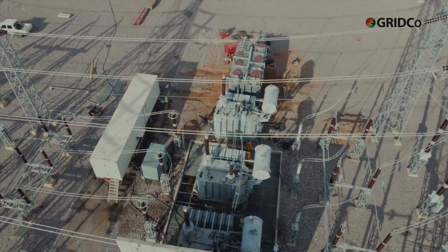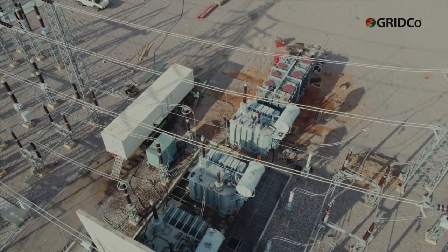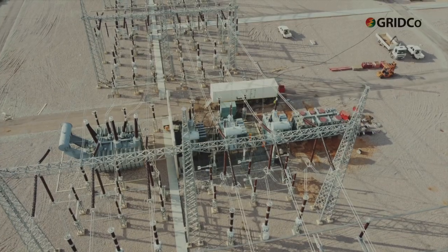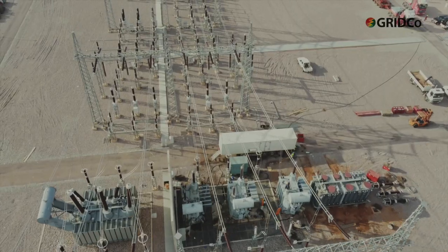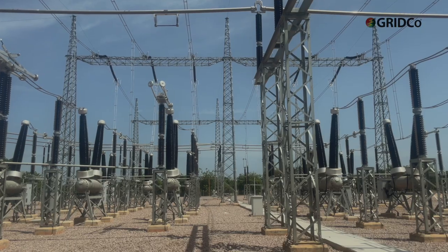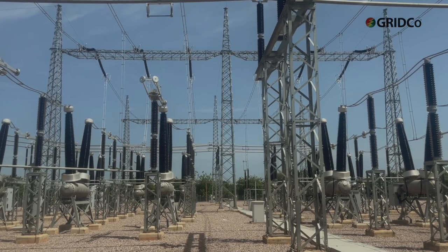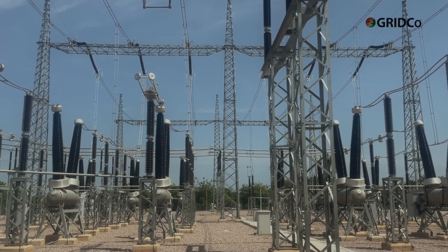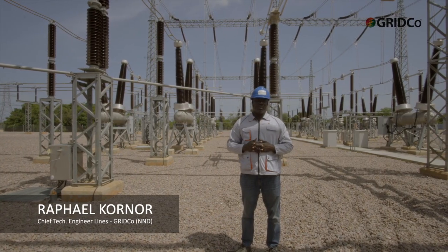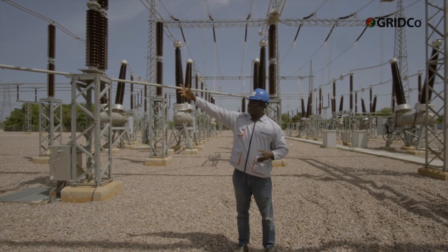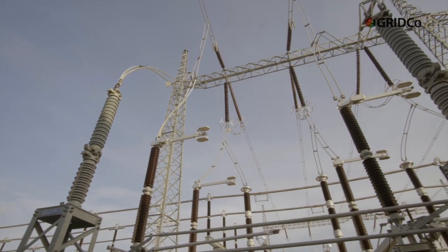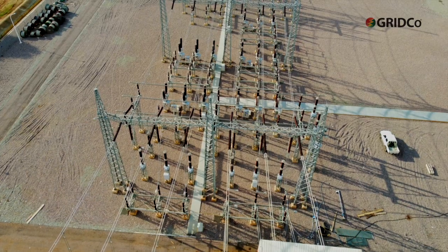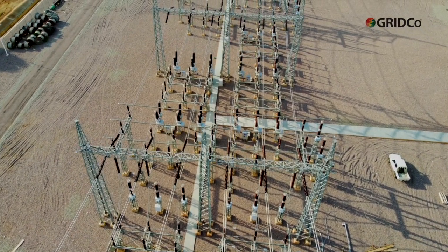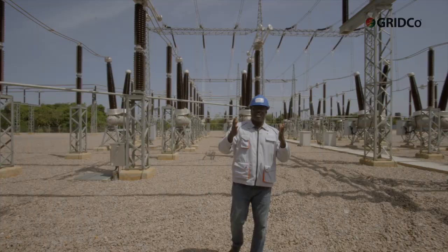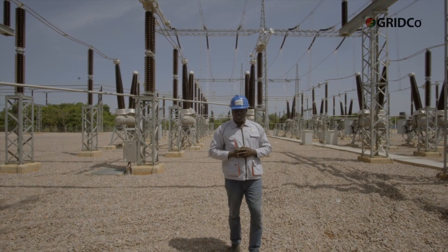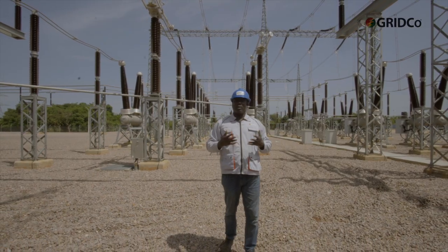The installed transformer, which is now permanently faulted, was a 330 kV to 225 kV voltage. However, the new one, which was brought from Elubu, is not the same, but rather 161 kV to 225. We needed to convert these two buses, one of them to 161 kV, so that we can be able to power the transformer that we are installing. And we will be dropping the 330 and hook it onto the 161 so that this bus will be energized for 161. The arrangement here was initially for 330, so we needed to change some parameters there so that it will conform with the new transformer that we have brought on board, which is 161 input, and then the output will be 225.